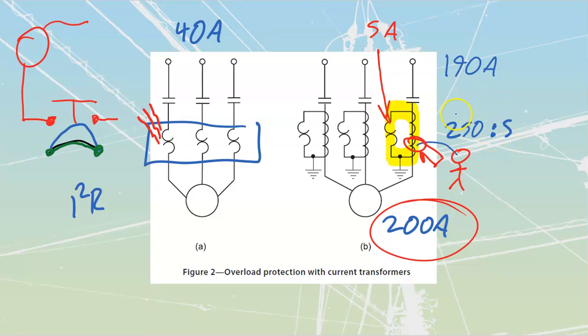You could also just take it and do 190 by 250 over 5, because that's the exact same thing. But when you do that, it's going to go and tell you that, or sorry, not multiply, divide by, I'm saying this thing backwards, but you get what's going on. We're going to go and divide it down to 1/50th because we're running through the CT over here, which would bring me out to a value of 3.8 amps off of it.